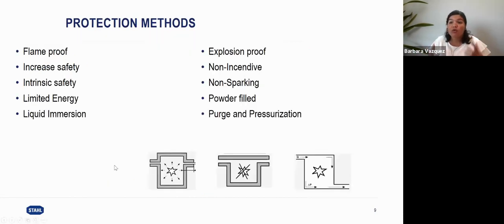Okay, so we do have several protection methods that we just discussed, but not all protection methods can be used in any hazardous area classification. These protection methods are recognized as per the standard. So that's why we say also it's very important to know what standard we are going to be working with. So for example, Class I Div.1, what can we use? Intrinsic safety, explosion proof, purge and pressurization. If we're talking about instrumentation, it's kind of hard to pressurize a proximity sensor, right? So we're mainly talking about intrinsic safety or explosion proof for Division 1.